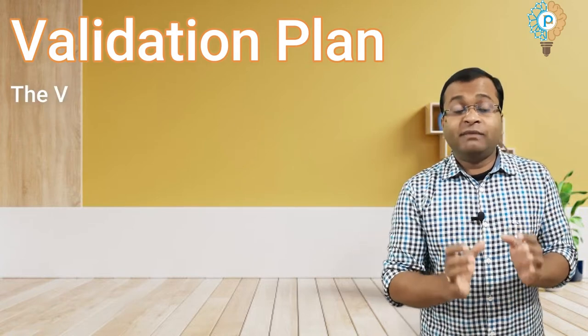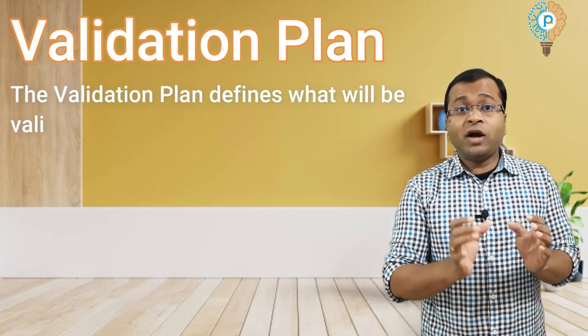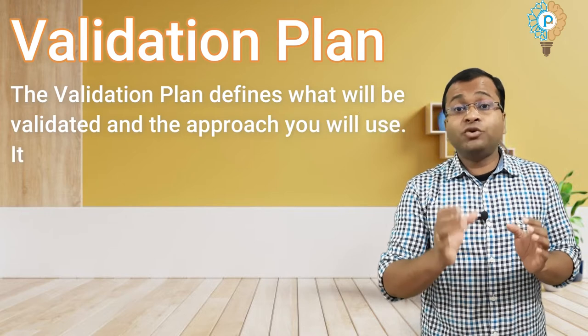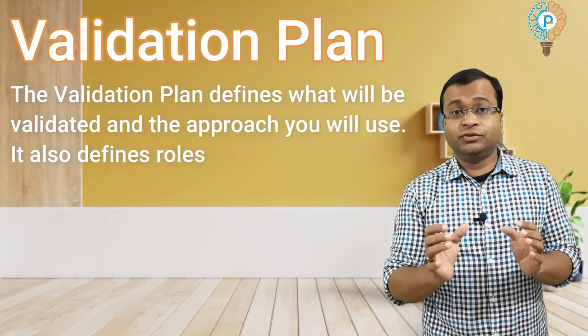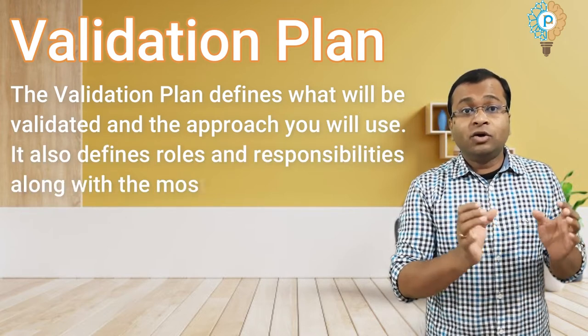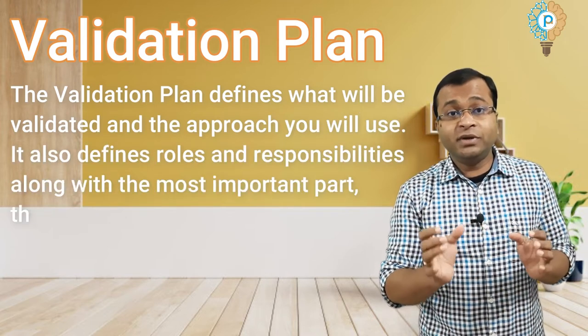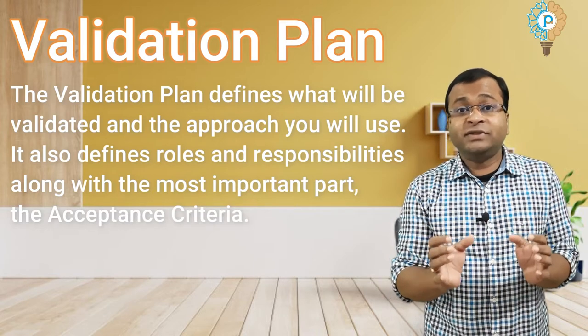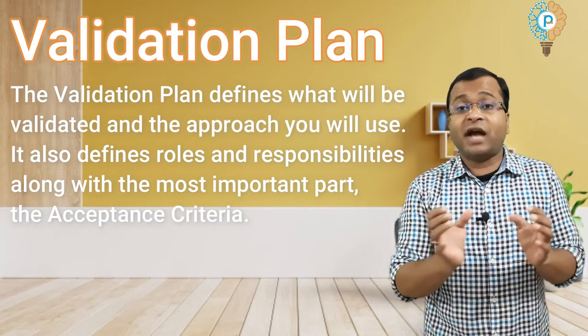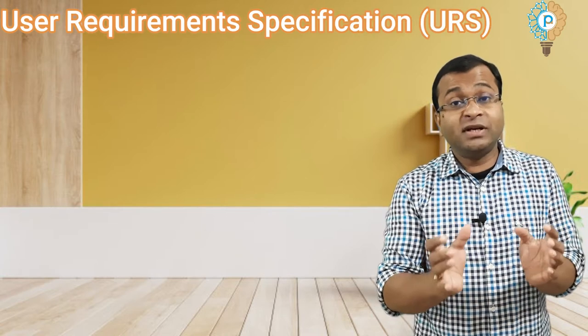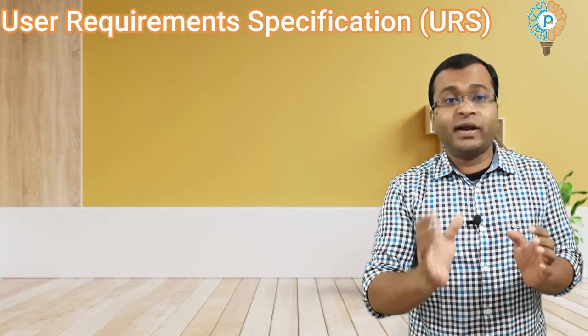The Validation Plan defines what will be validated and the approach we will use. It also defines roles and responsibilities along with the most important part, that is the acceptance criteria. Next is the User Requirement Specification, that is the URS.